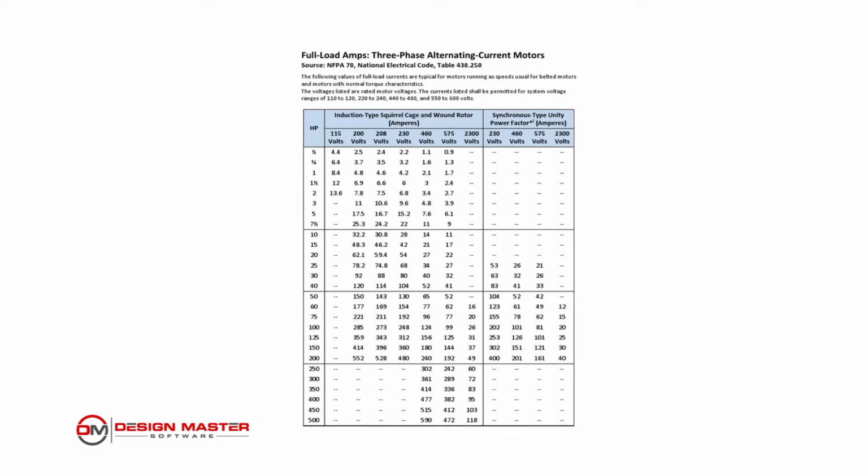How does the electrical designer use the rated horsepower and the brake horsepower in their design? Well, ironically, the National Electric Code handles this directly with Table 430.250, for example, for three-phase motors. Actually, there's several tables there in Section 430, and the National Electric Code actually prescribes the amps for each rated horsepower that the engineer has to use.